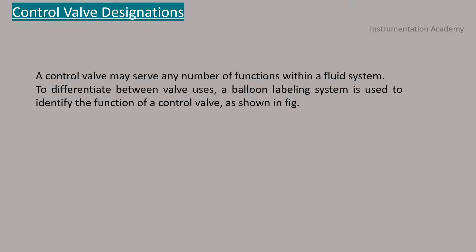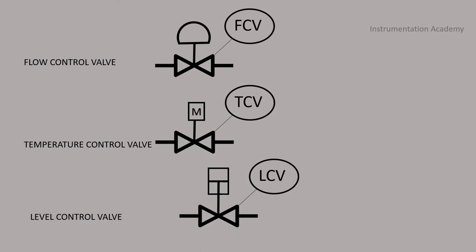Control valve designations. A control valve may serve any number of functions within a fluid system. To differentiate between valve uses, a balloon labeling system is used to identify the function of a control valve as shown in the figure. The common convention is that the first letter used in the valve designator indicates a parameter to be controlled by the valve. The second letter is usually a C and identifies the valve as a controller. And the third letter is a V to indicate that the piece of equipment is a valve.